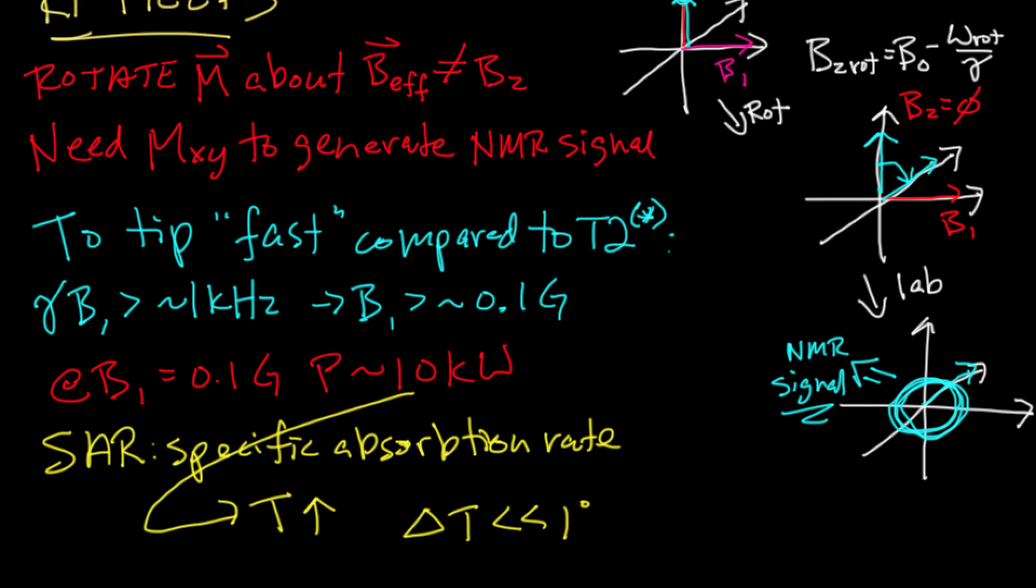The geometry of the coils that make the B1 fields are very much complementary to those of the gradient coils. In that for gradient coils, the only component of field that matters is the z component field. For RF pulses, the only component of the magnetic field that matters is the transverse components. So typical geometry of an RF coil that produces RF pulses is something like this, and as you can see, the primary magnetic field component that it generates will be transverse.